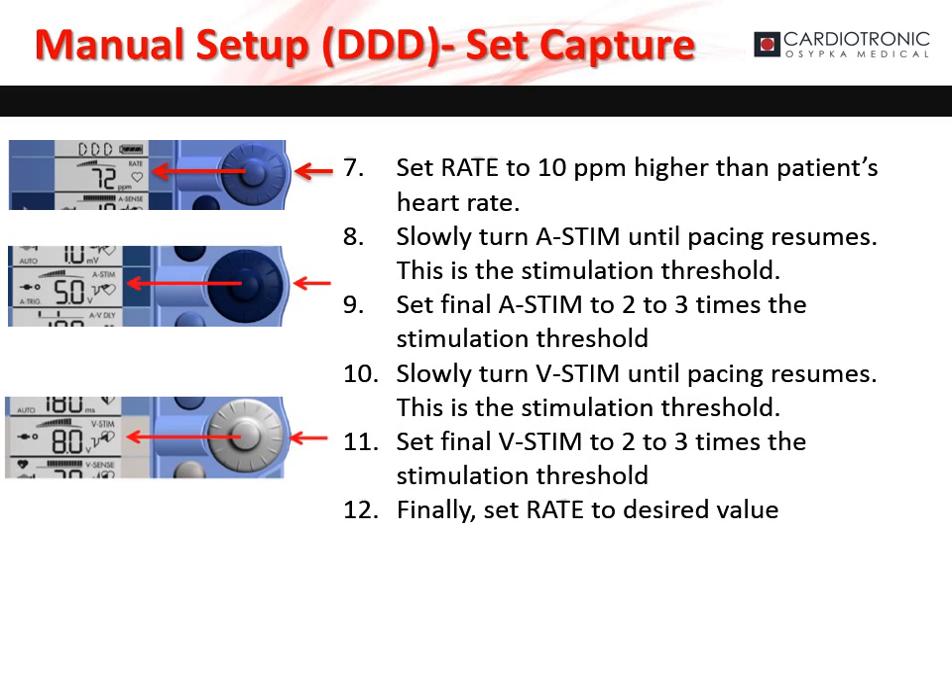To set the capture threshold, monitor the ECG and set the rate to 10 beats per minute higher than the patient's heart rate to ensure capture. Increase A-STIM until capture — this is the atrial capture threshold. Set A-STIM to two to three times higher than the atrial capture threshold. Increase V-STIM until capture — this is the ventricle capture threshold. Set V-STIM to two to three times higher than the ventricle capture threshold. Finally, set the rate to the desired value.